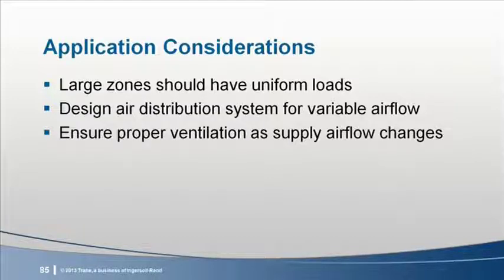With that said though, asymmetric ductwork is not necessarily a showstopper for using single-zone VAV. It just means that the zone is more likely to experience unequal airflows between diffusers as the fan speed changes. The next one we already discussed in detail. You need to provide some means to ensure proper ventilation to the zone as supply airflow changes. John described a few possible approaches earlier. For some types of equipment, two-position or proportional damper control might be used. Larger systems may use actual airflow measurement. Or when a dedicated outdoor air system is used, consider delivering the conditioned outdoor air directly to each zone, rather than to the inlet of the local equipment.